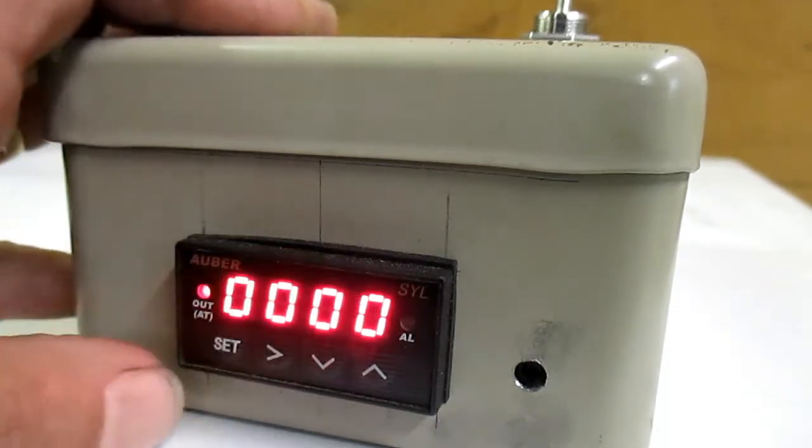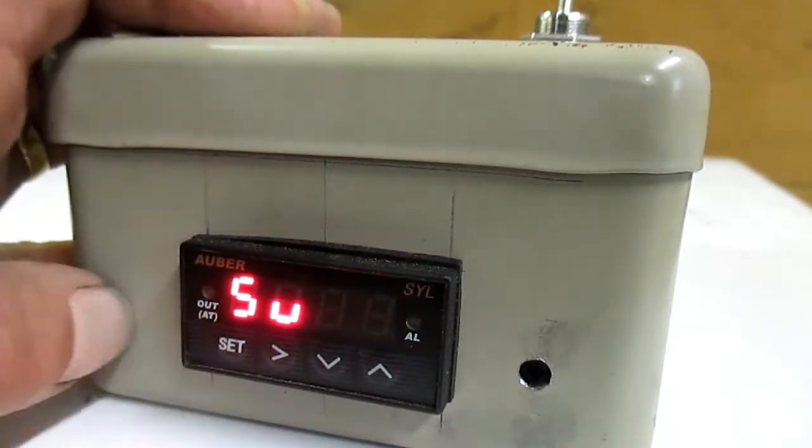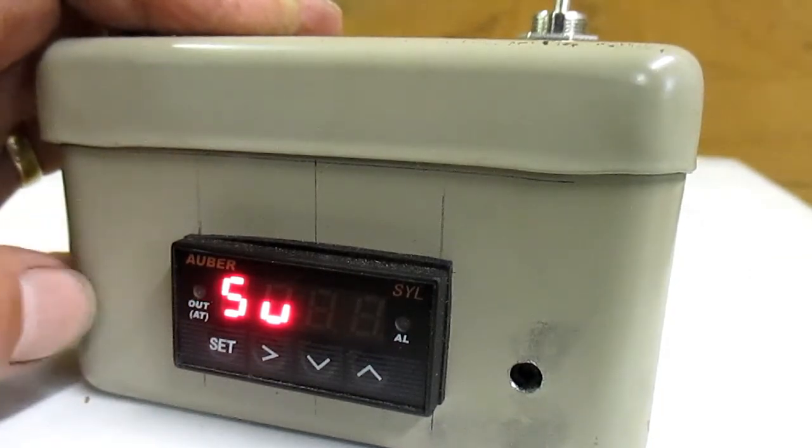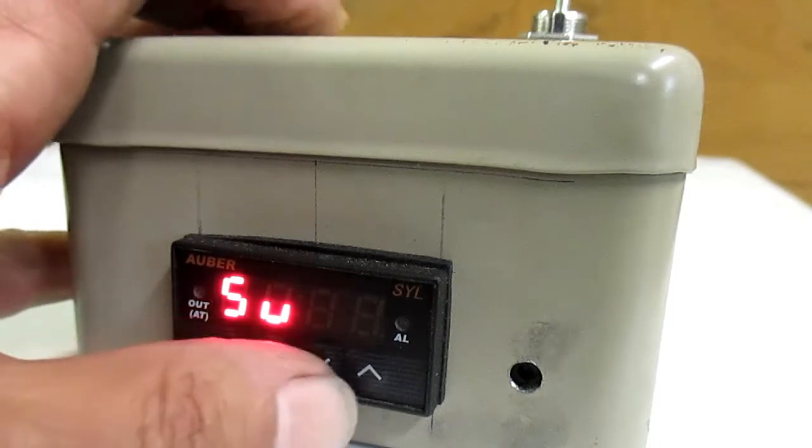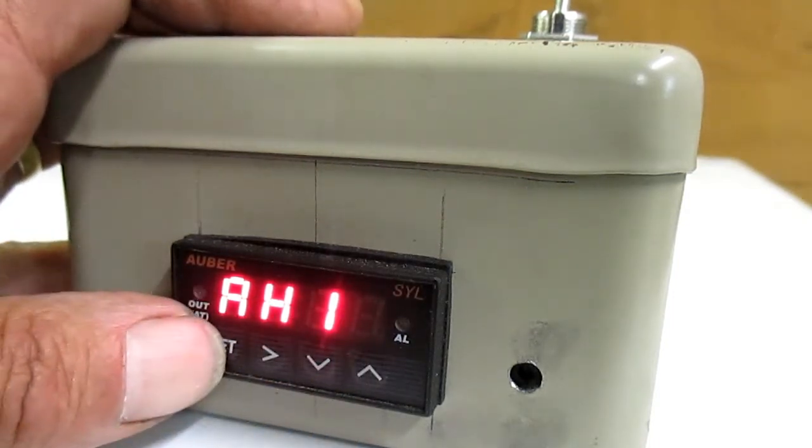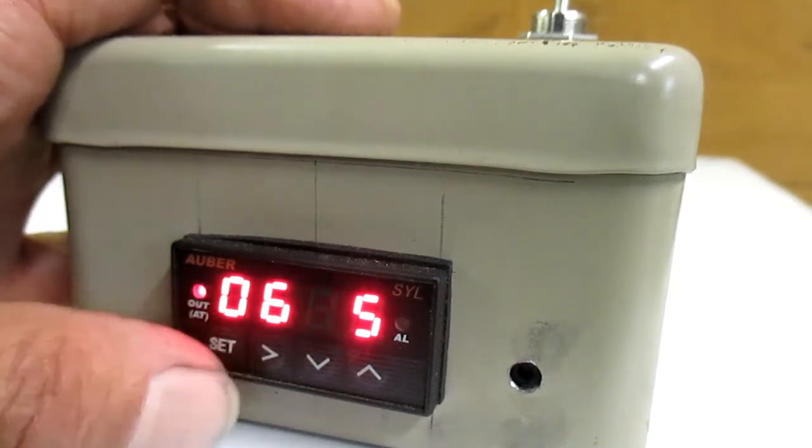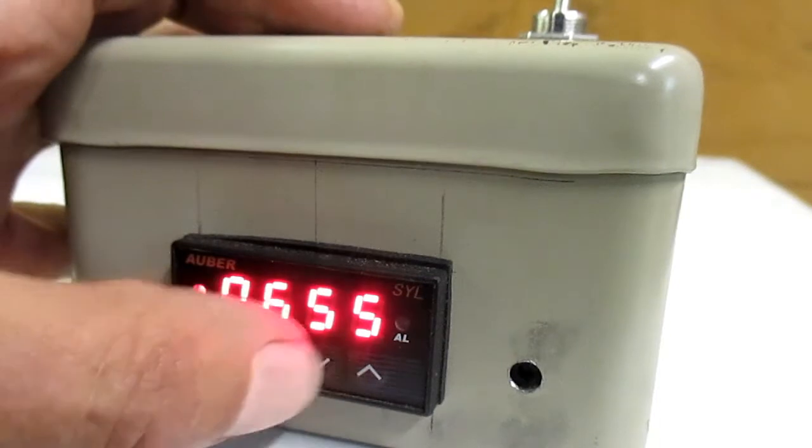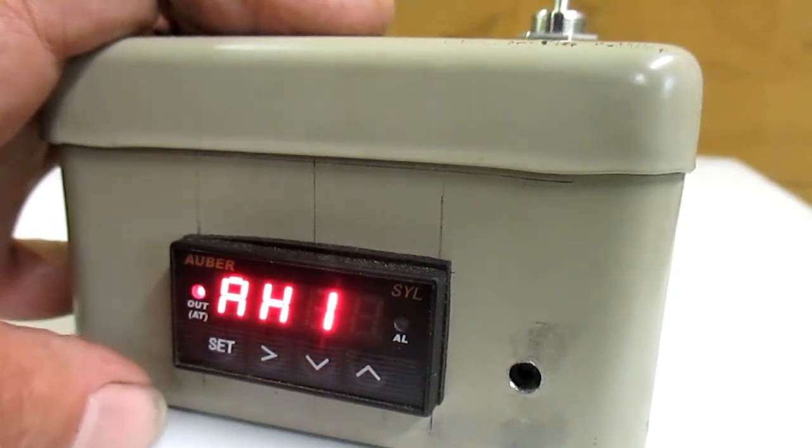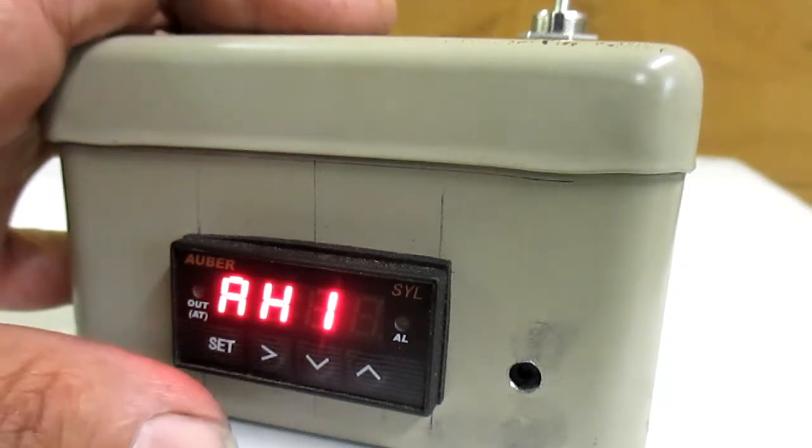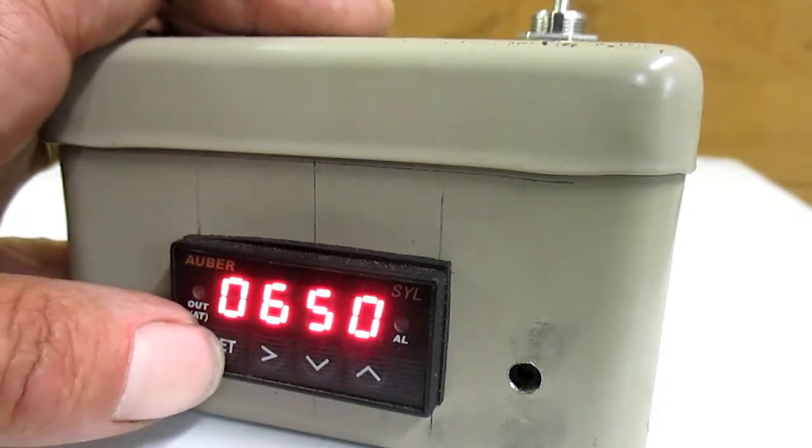First thing I do is I press the set button. I have to enter in 0001. So I go over, over, over, and up. There's the one. Then I hit set again. Now from here what I'm looking for is AH1. That stands for alarm high, and this is the first alarm because you can set two alarms for this. We'll push the up. There's the high. Then we press set.